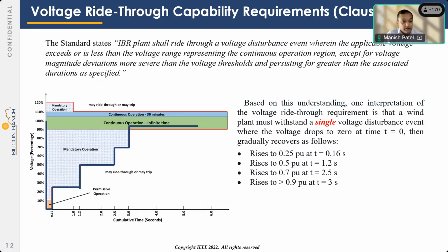It is then the interpretation, at least in my mind, that if you had a single voltage disturbance event where voltage drops from nominal to zero, rises at 160 milliseconds to 25%, at 1.2 seconds to 50%, and hugs the boundary of this LVRT, then the IBR is required to ride through. That is okay if that's the correct interpretation.